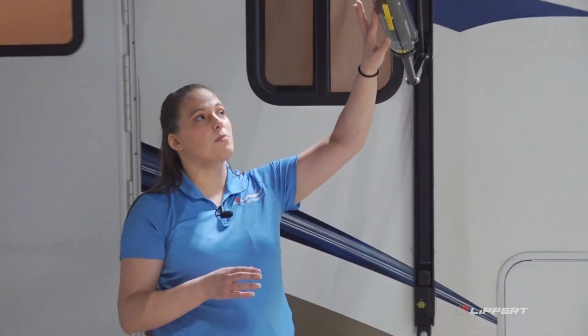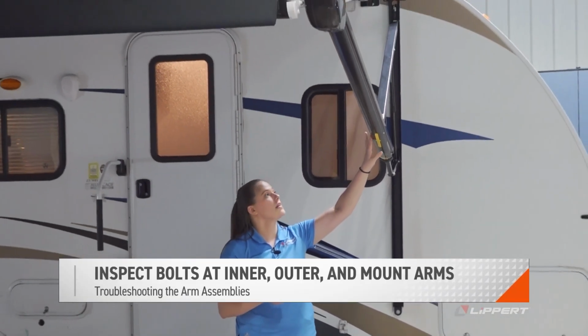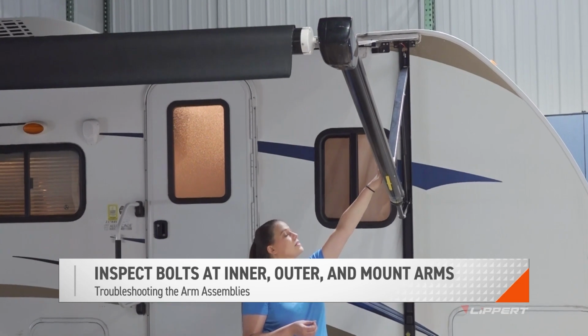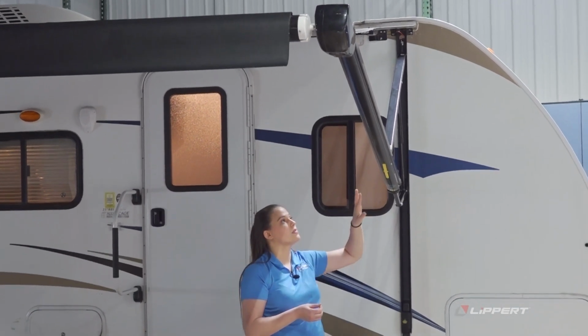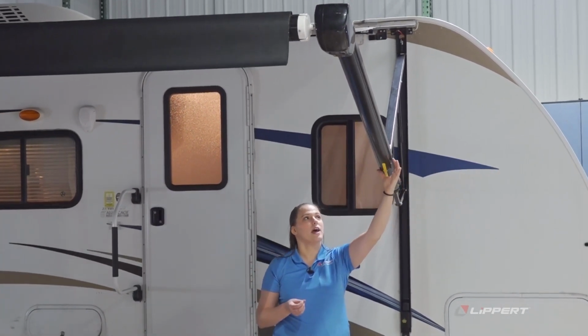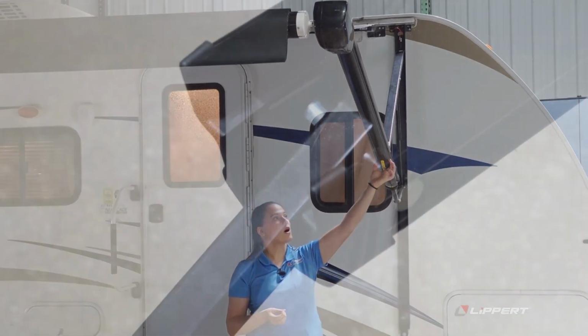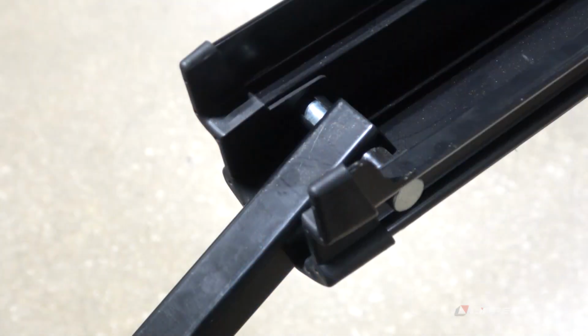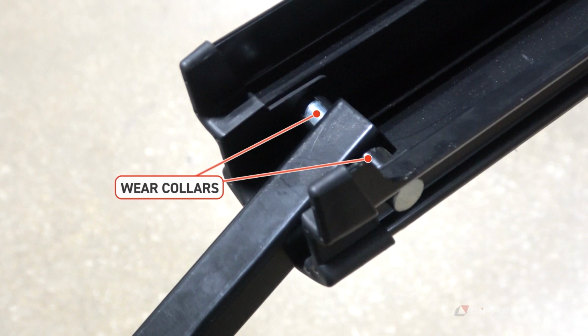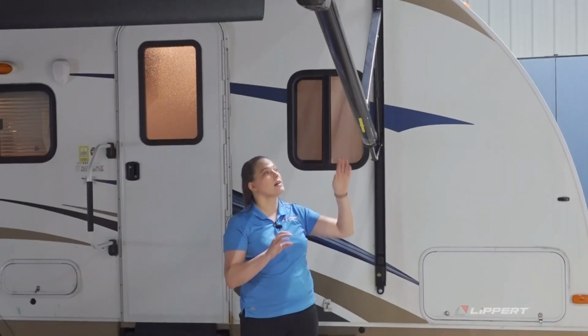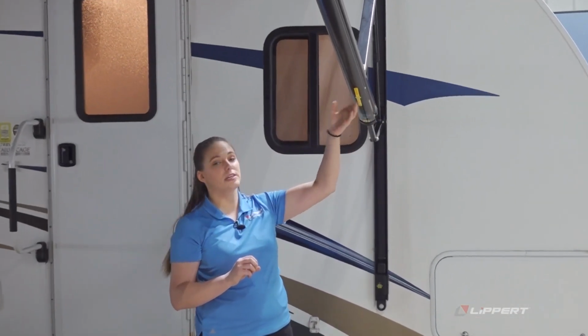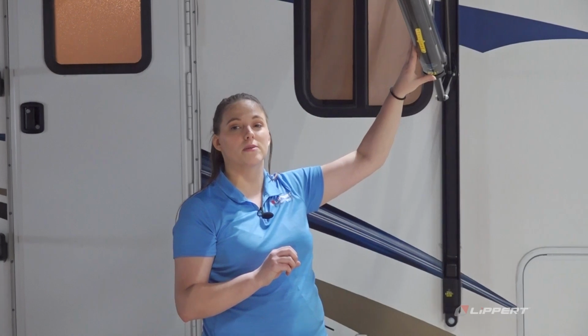The parts that you want to pay attention to are the bolts that connect the arm assembly together at the outer arm, the inner arm, and the mount arm. On these bolt assemblies, you should have a bolt on one side, a lock washer on the other. In between the arm assemblies, you should have wear collars. These wear collars are little plastic spacers that are on those bolts, and those maintain the space between each of the components for the arm assembly.